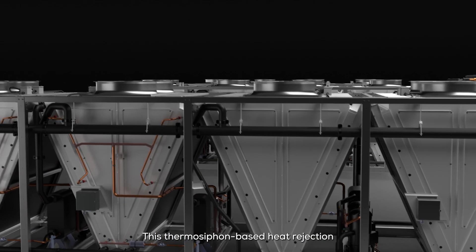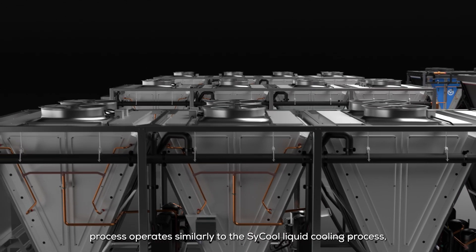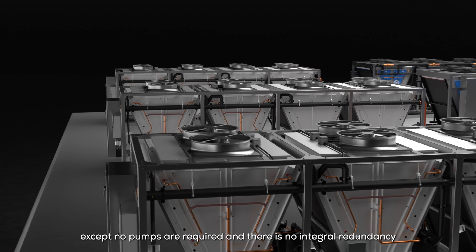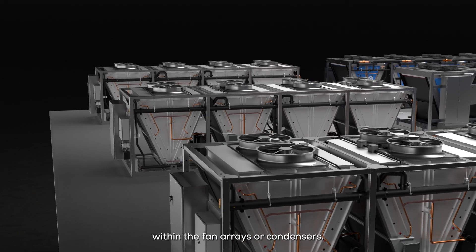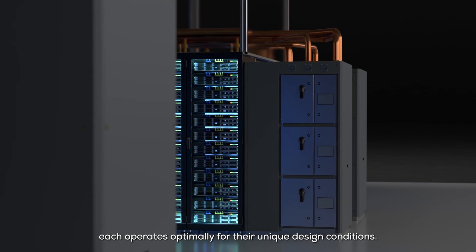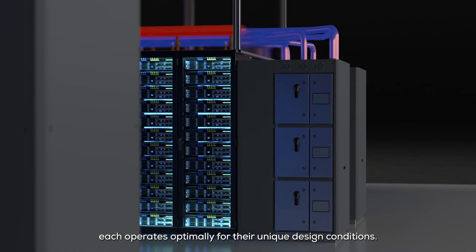This thermosyphon-based heat rejection process operates similarly to the SyCool liquid cooling process, except no pumps are required and there is no integral redundancy within the fan arrays or condensers. By decoupling the air and liquid cooling processes, each operates optimally for their unique design conditions.